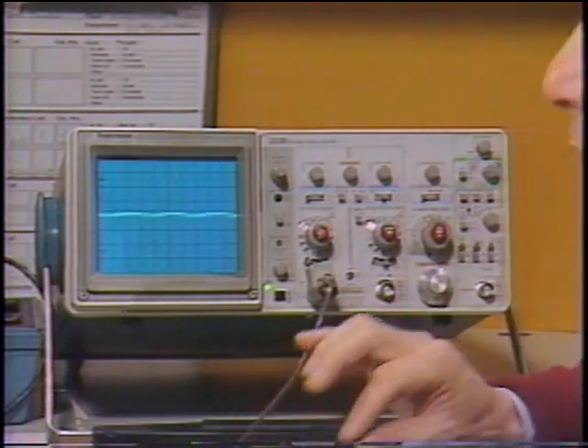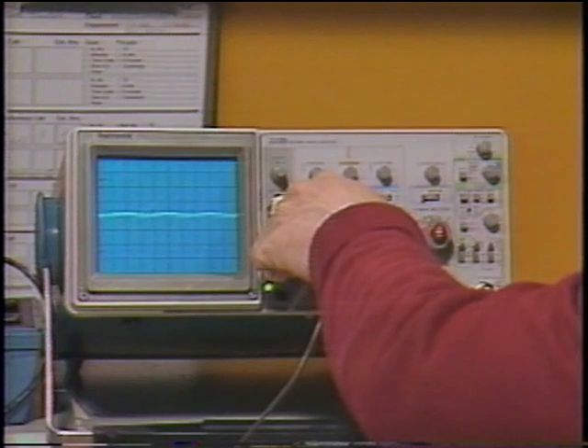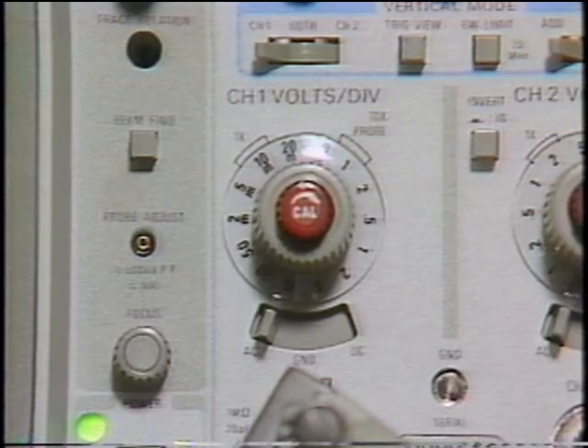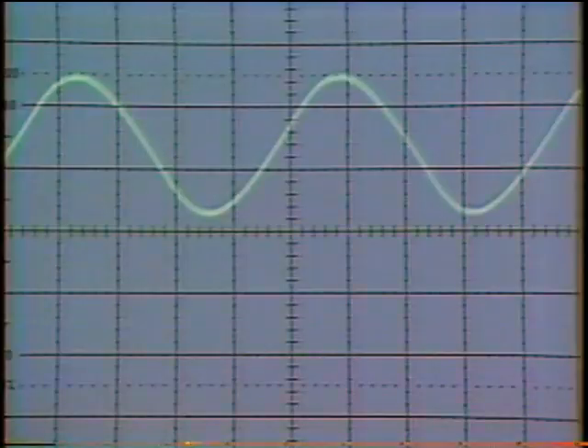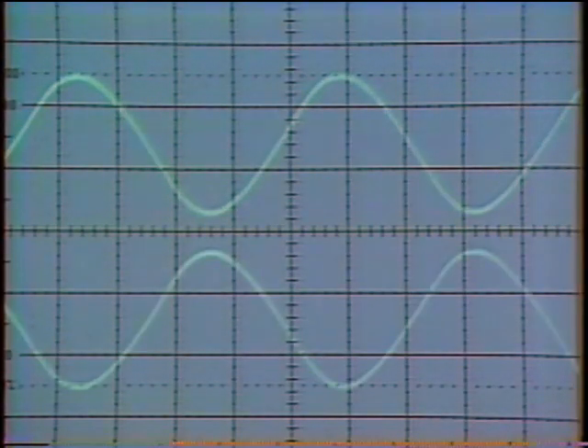What I need to do now is select a greater sensitivity — so I turn the volts per division, and the squiggly line becomes a sine wave. By attenuating or reducing some signals and amplifying others, ratios of a million to one are possible, and ratios of 10,000 to one are standard. Why are there two volts per division controls? So I can display two different signals at the same time. Often different events are related, and the best way to see what is going on is to see both of them at the same time. Each vertical channel has its own related controls nearby, much like your stereo has special switches to change sources and functions.